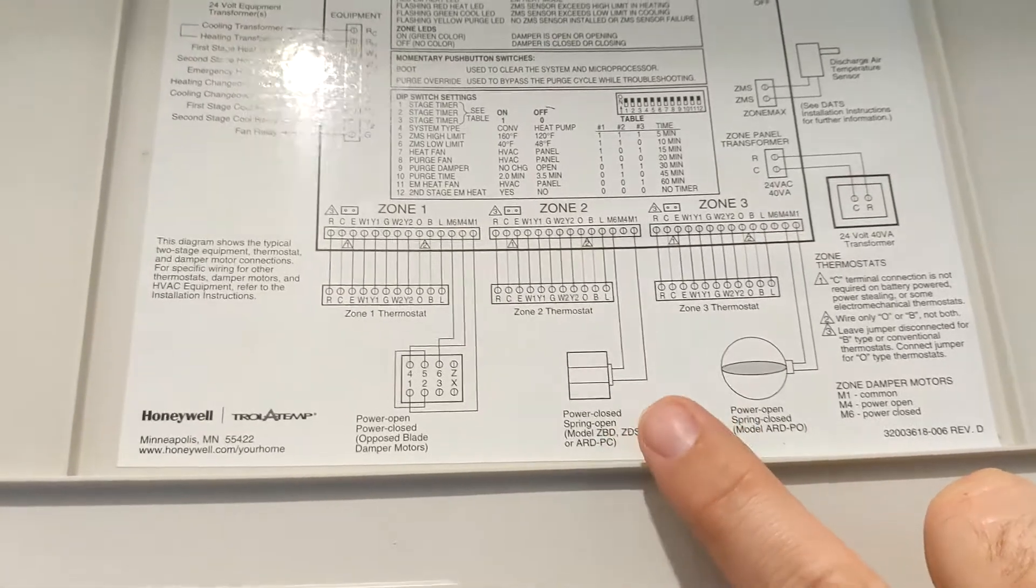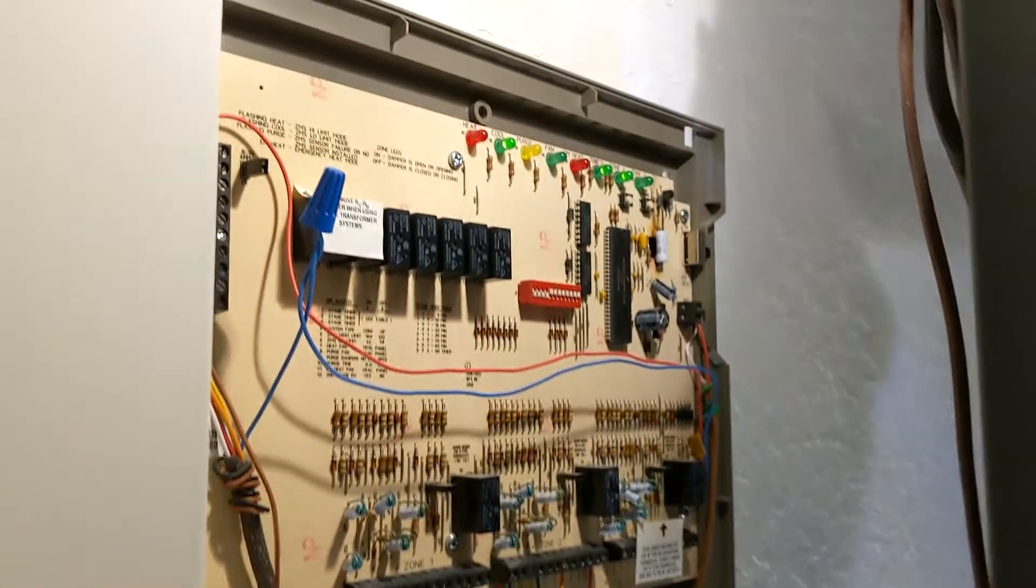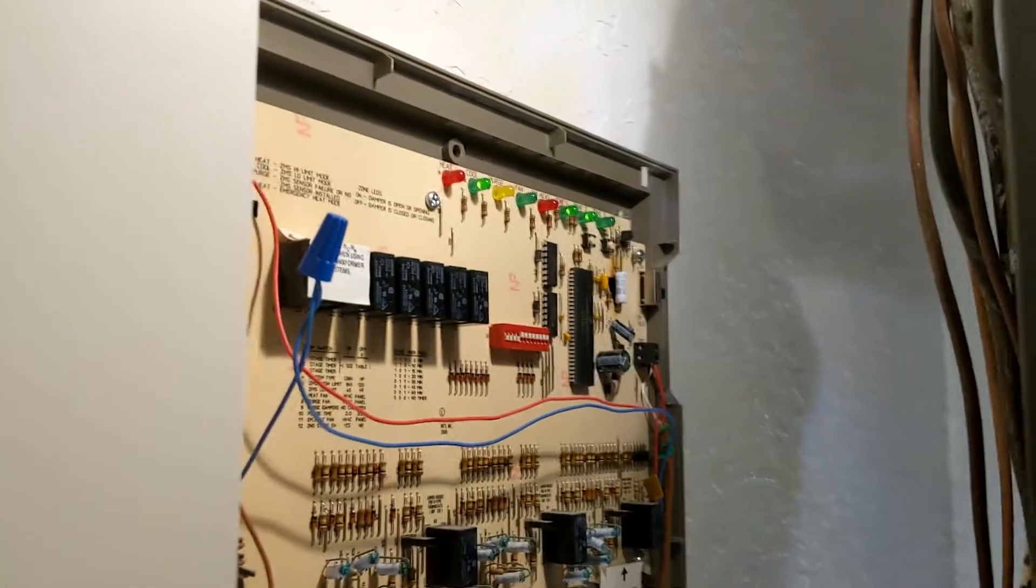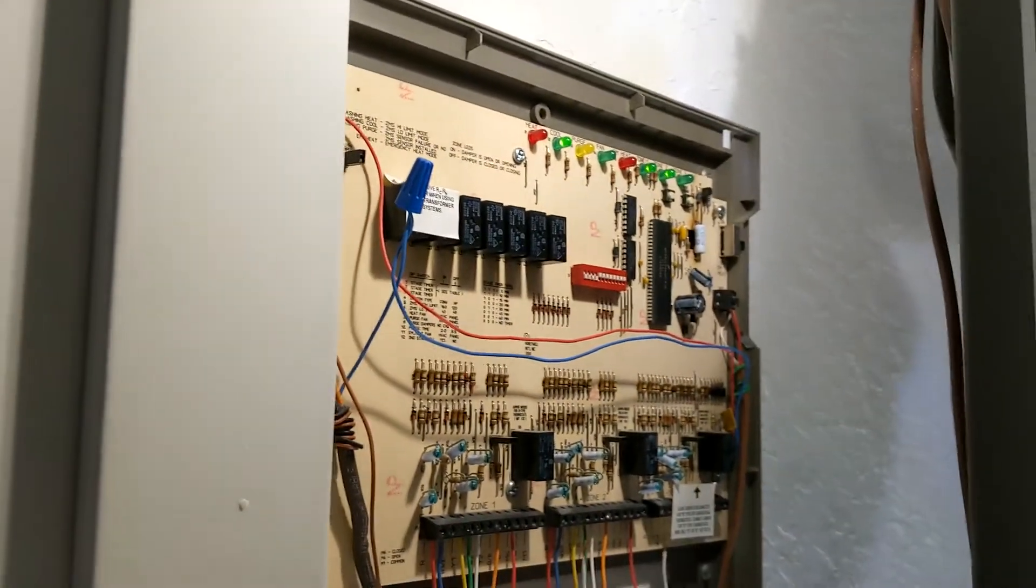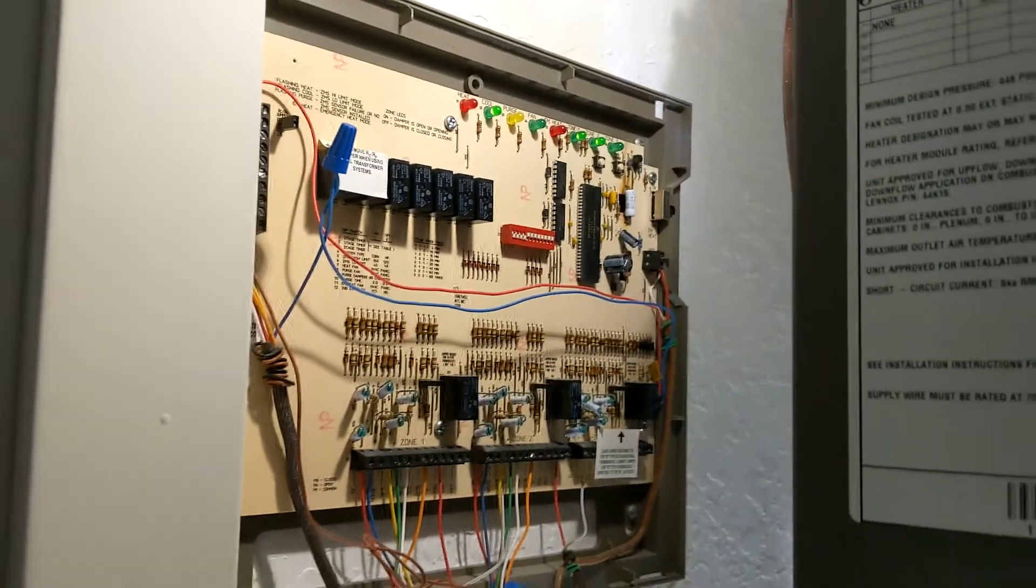So what that's referring to is when there's no power to that damper, it's going to remain open. That's what we wanted to do because our unit kept freezing up when zone two would operate. It's just some malfunction with the zoning board.